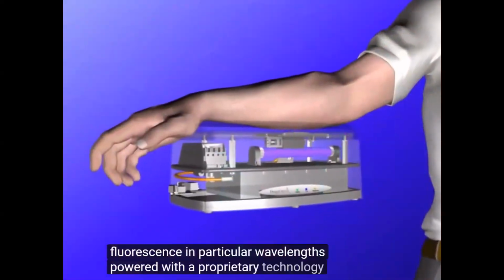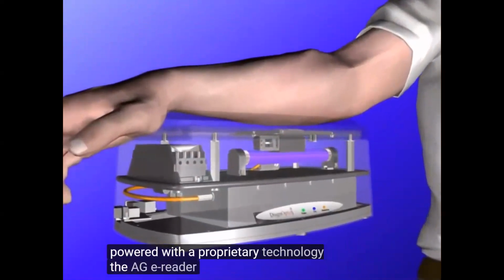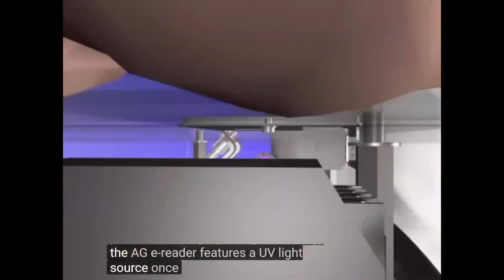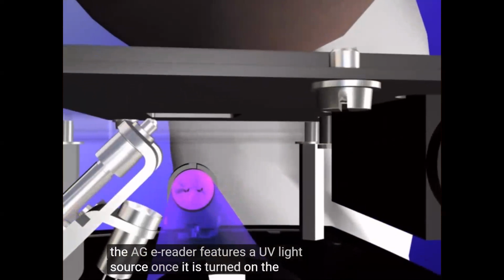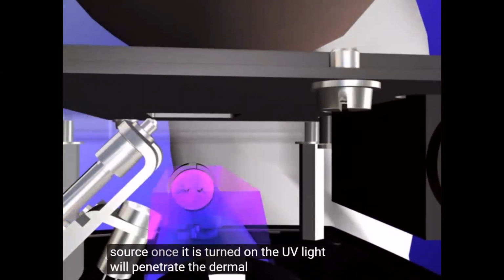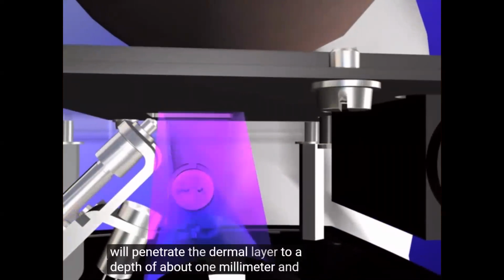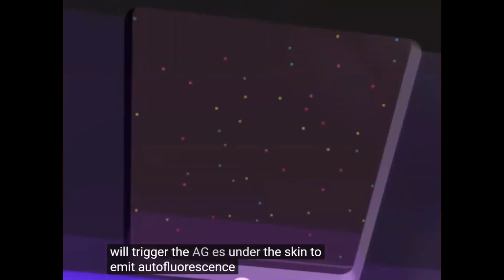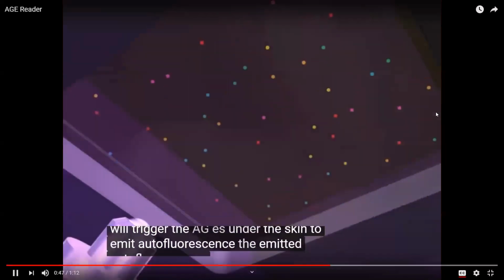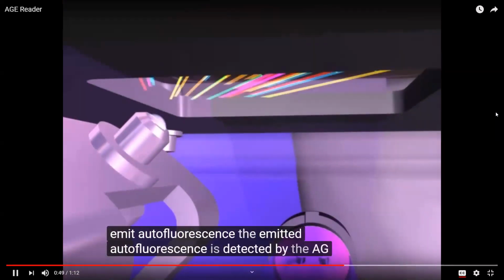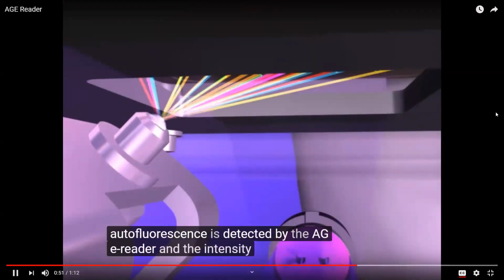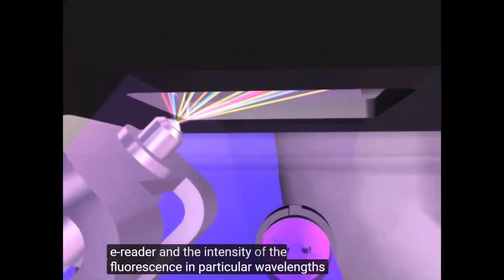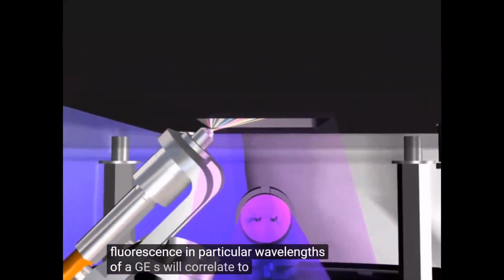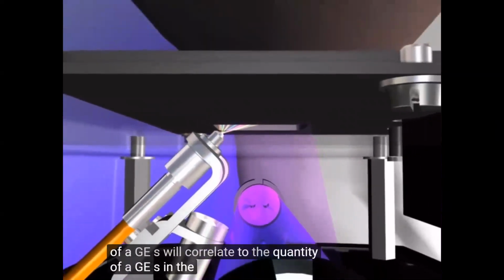Powered with proprietary technology, the AGE reader features a UV light source. Once it is turned on, the UV light will penetrate the dermal layer to a depth of about 1 millimeter, and this will trigger the AGEs under the skin to emit autofluorescence. The emitted autofluorescence is detected by the AGE reader, and the intensity of the fluorescence in particular wavelengths of AGEs will correlate to the quantity of AGEs in the tissue.